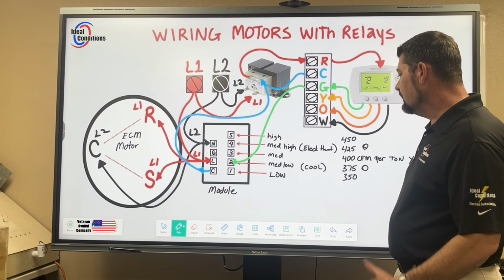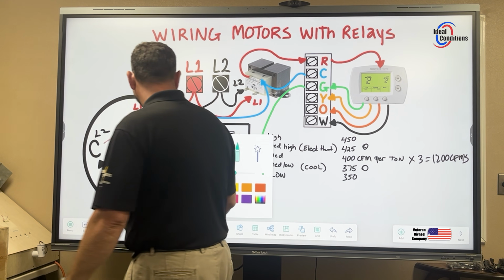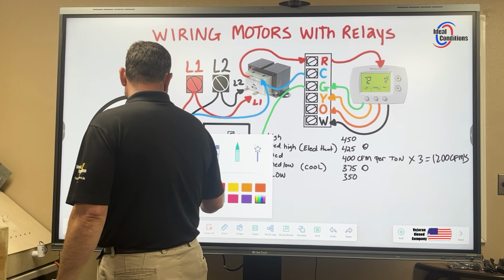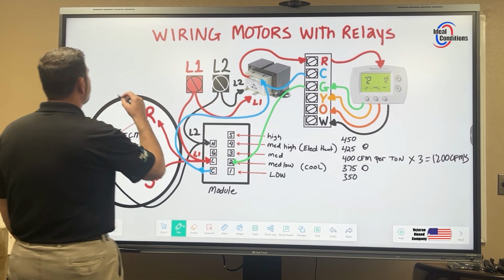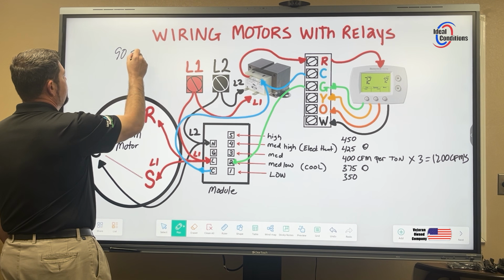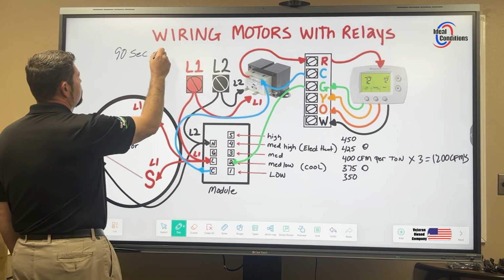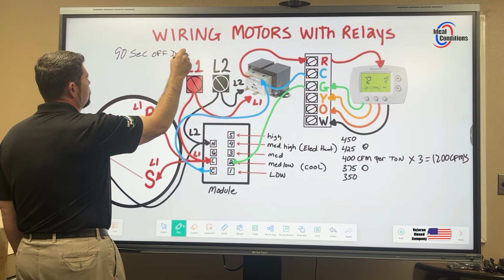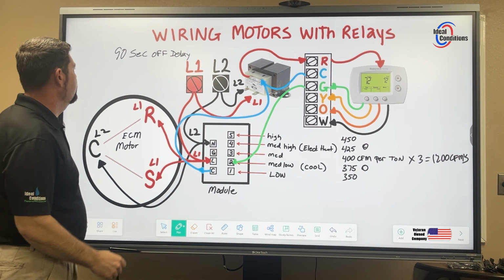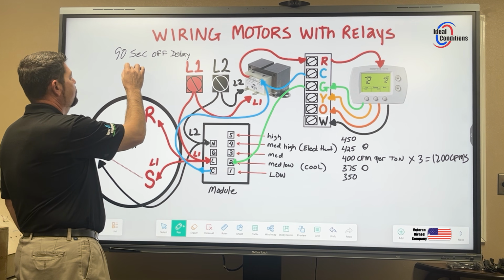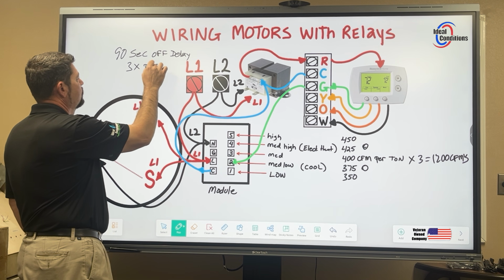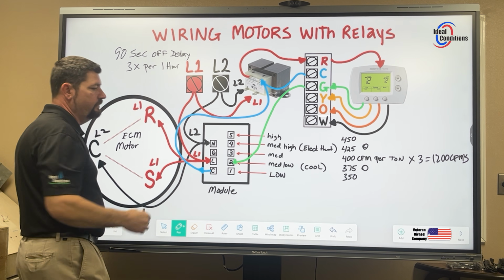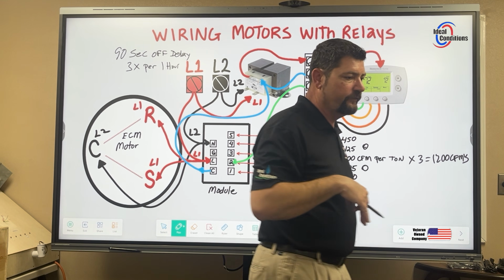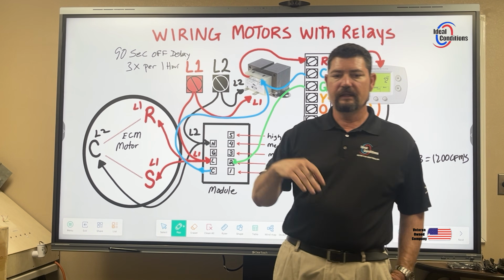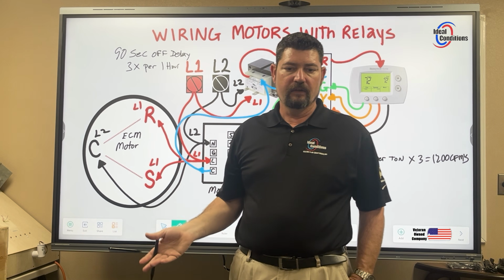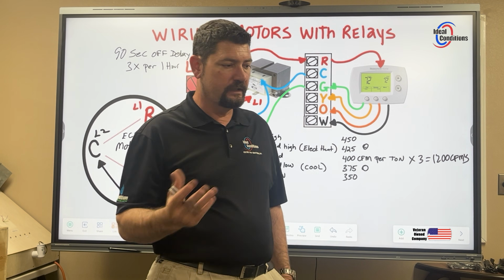Getting into that 90 seconds, if you want to see what that looks like here. If we said 90 seconds was our off delay. All right, 90-second off delay. If we shut off 3 times an hour, that would mean it ran for 10 minutes, it shut off for 10 minutes, it ran for 10 minutes, it shut off for 10 minutes, it ran for 10, shut off for 10, and it kept on doing that.